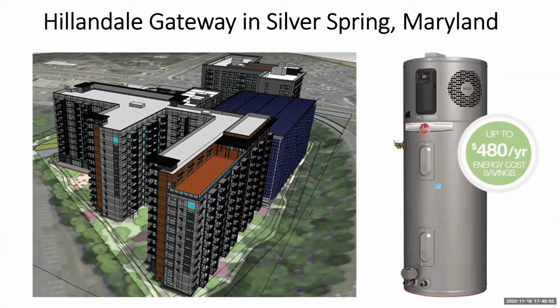Well, it would be at the high COP. You know, when you transfer heat in, there's some inefficiency captured in the COP. And then when you continue to transfer heat, so you basically might lose about 10 to 15% of COP, coefficient of performance, its efficiency, by doing that double transfer. But when you enter it into the software, you should have a COP of 3 or greater, is how that would work in the wintertime. And assuming it's not like crazy cold outside. And it's rarely actually crazy cold outside. It's just sometimes it's bad.